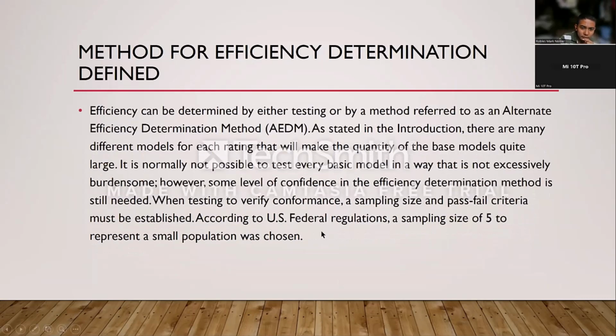Method for efficiency determination, defined as the AEDM, the alternate efficiency determination method, stated in the introduction that models for each rating will make the quantity of the base models quite large. It is normally not possible to test every basic model in a way that is not excessively burdensome. When testing to verify, a sample size and pass-fail criteria must be established. According to U.S. federal regulations, a sampling size of 5 to represent a small population must be observed.